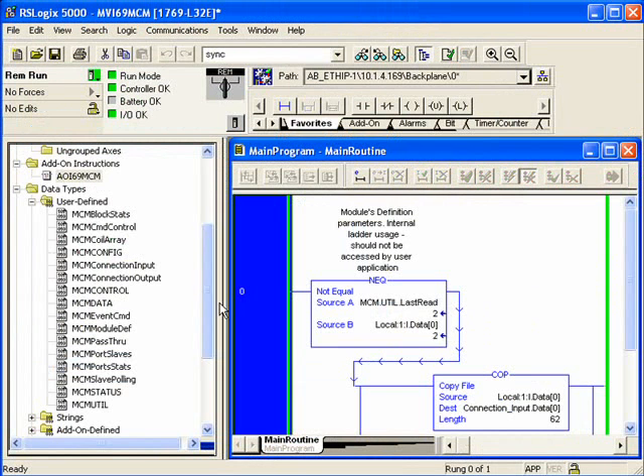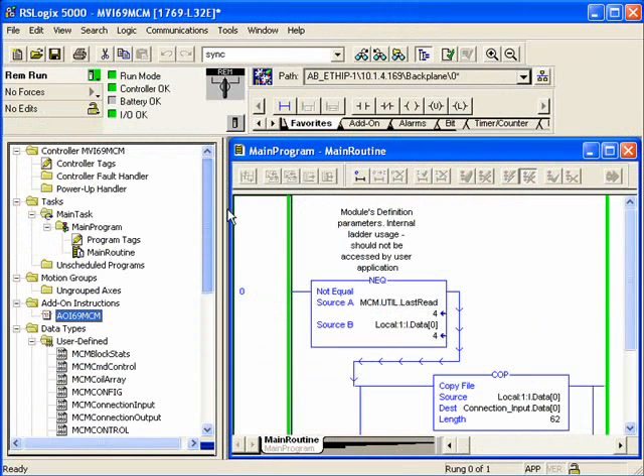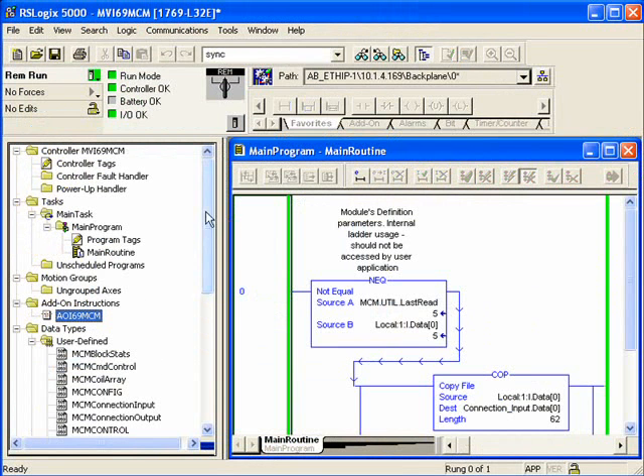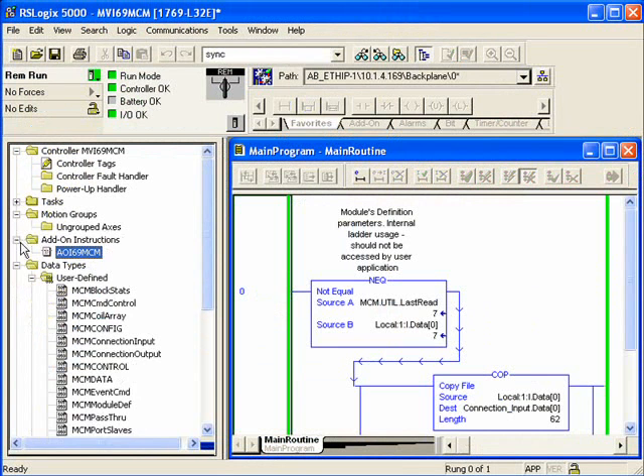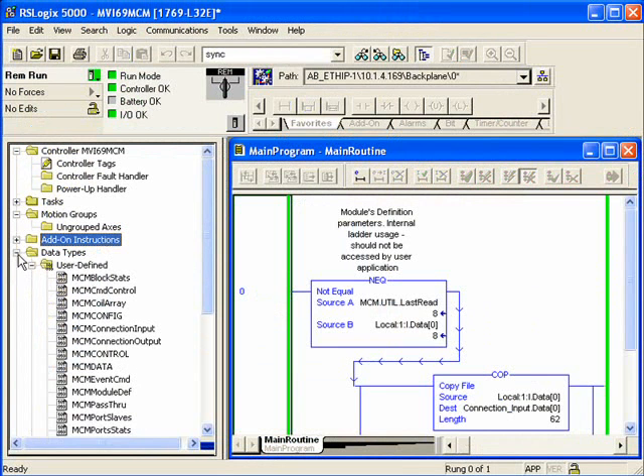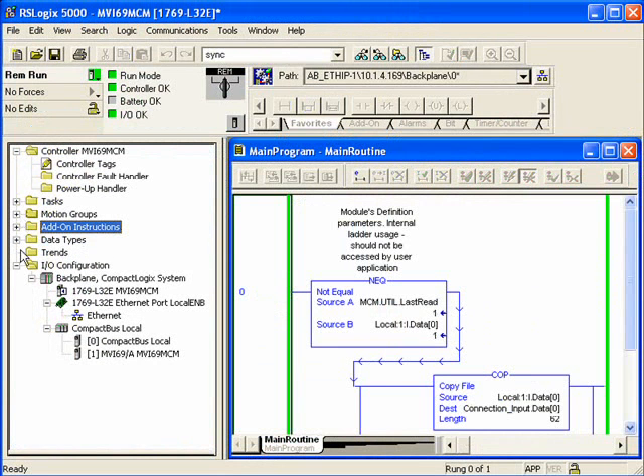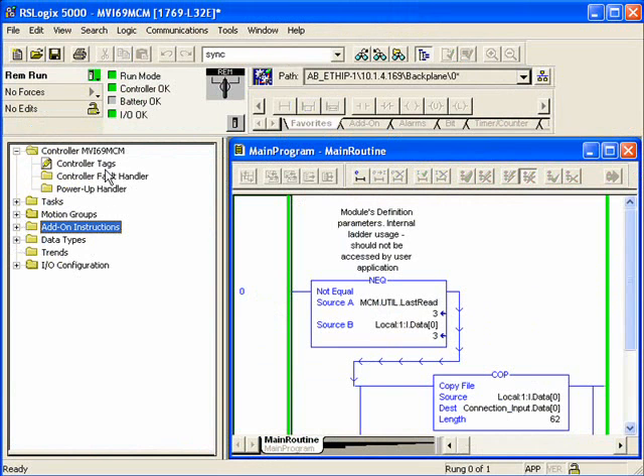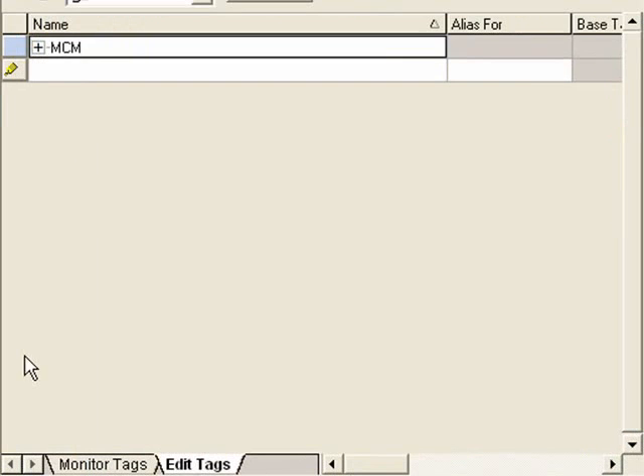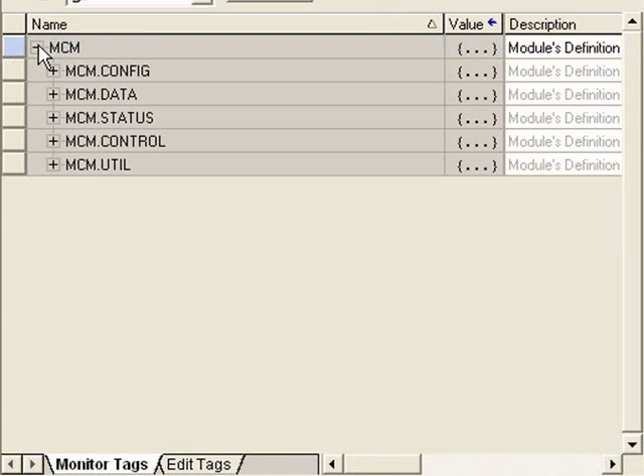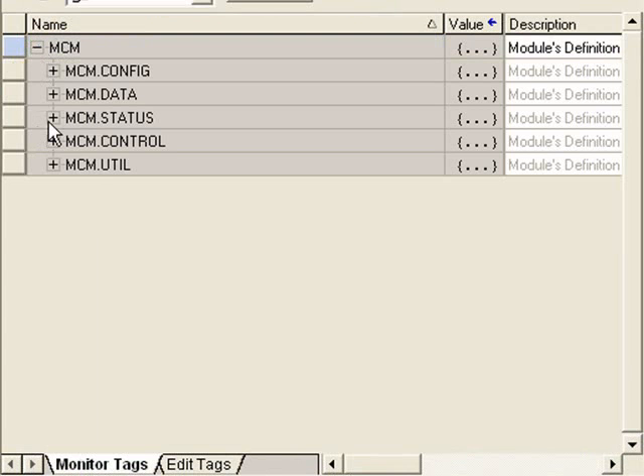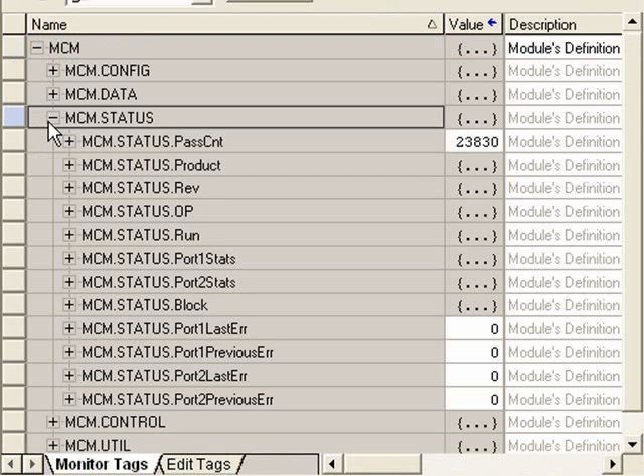Now I'll go to the controller tags just to verify everything's looking good. I see I don't have any I.O. lights flashing. So I think everything is running as expected. So we'll go into the controller tags. We'll go to the MCM tag and then Status. And then we see the Pass Counter Counting. That tells me that the module is actively communicating to the processor and vice versa.